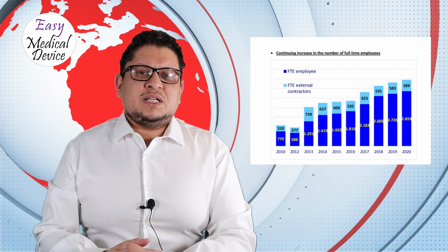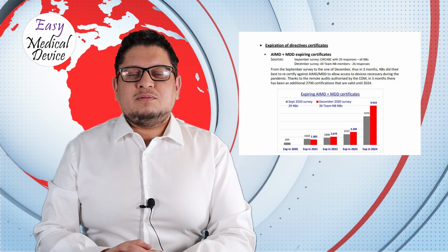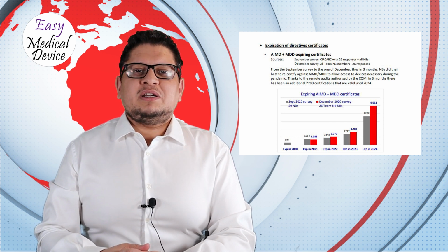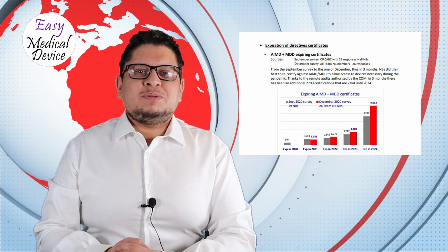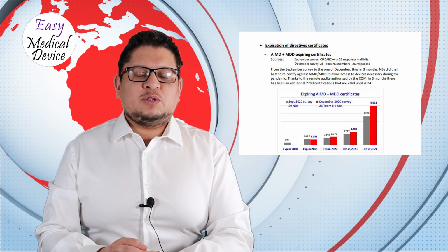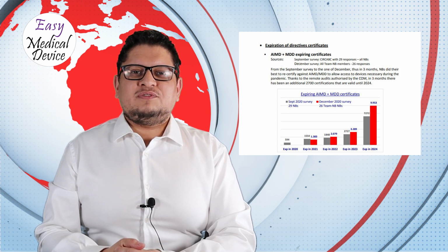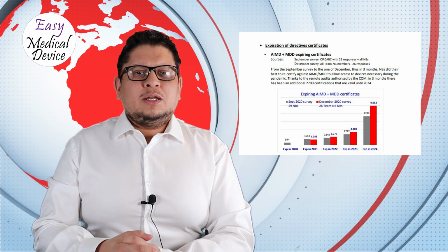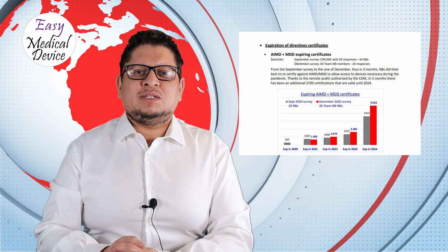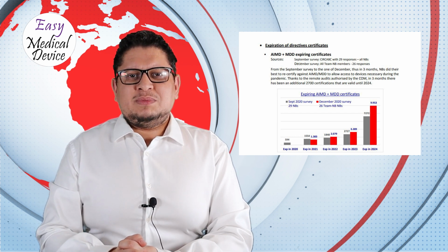One more interesting piece of information is that a majority of the CE certificates under MDD will expire by 2024. It means that a big number of manufacturers will arrive and ask the notified body at exactly the same time to get certified. So don't make the mistake: even if your certificate expires in 2024, don't wait until 2024 to get certified under EU MDR.